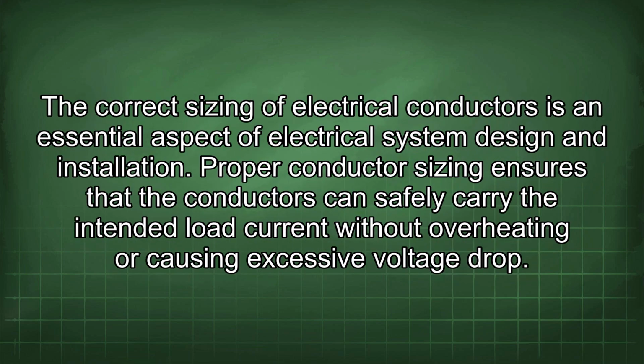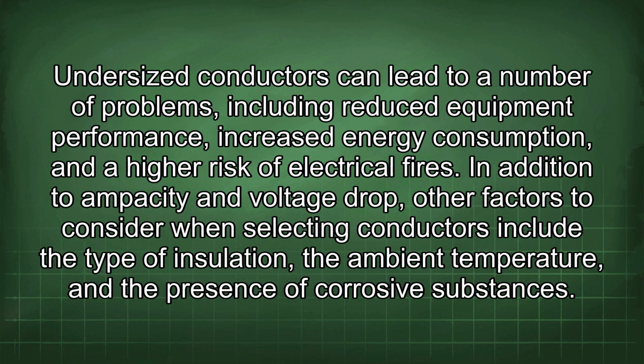The correct sizing of electrical conductors is an essential aspect of electrical system design and installation. Proper conductor sizing ensures that the conductors can safely carry the intended load current without overheating or causing excessive voltage drop. Undersized conductors can lead to a number of problems, including reduced equipment performance, increased energy consumption, and a higher risk of electrical fires. In addition to ampacity and voltage drop, other factors to consider when selecting conductors include the type of insulation, the ambient temperature, and the presence of corrosive substances.